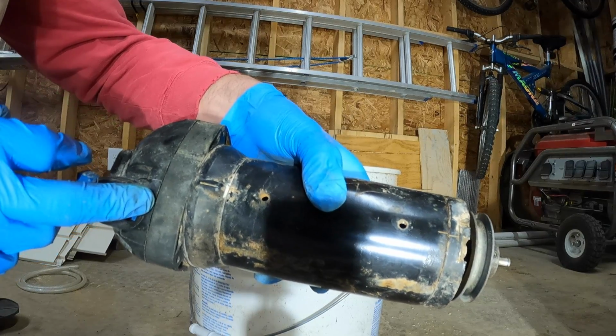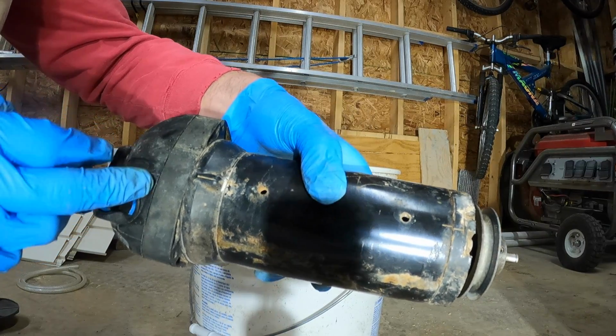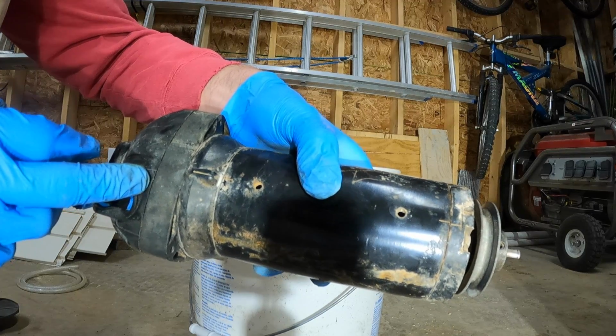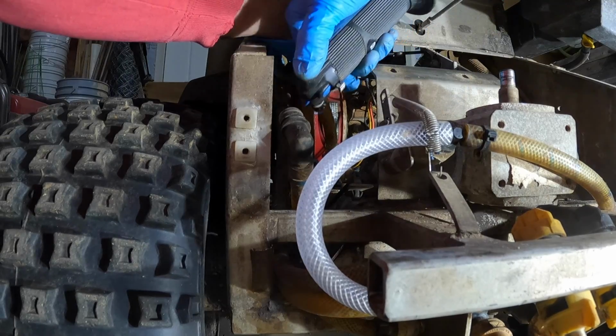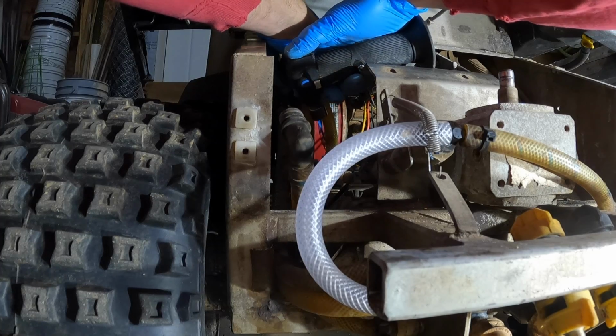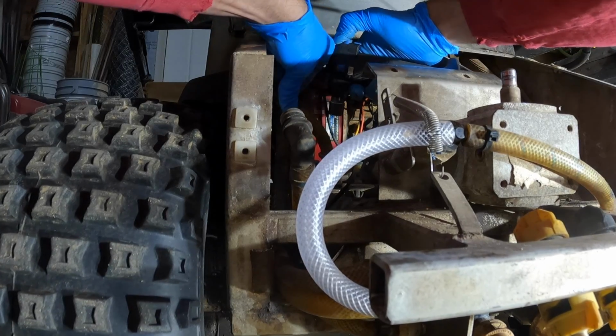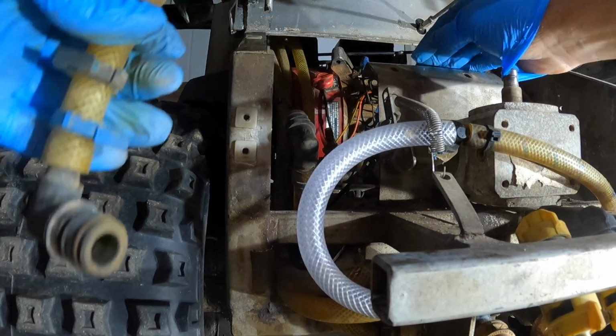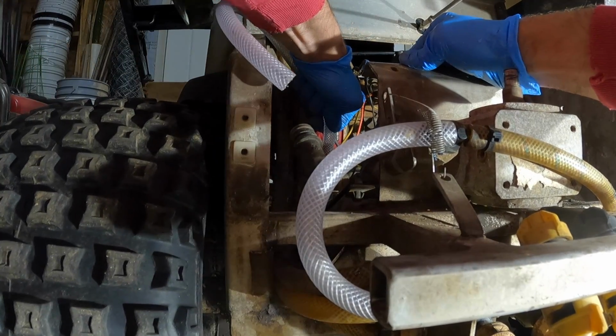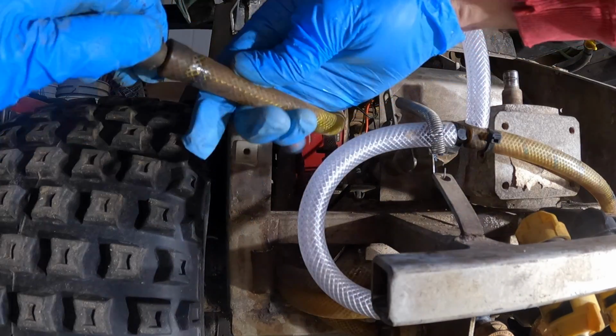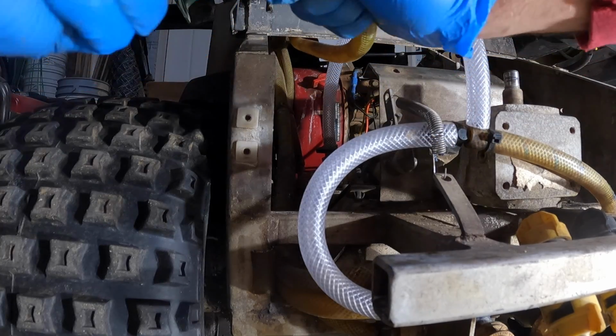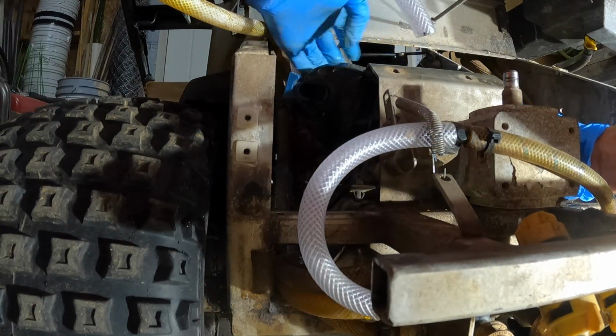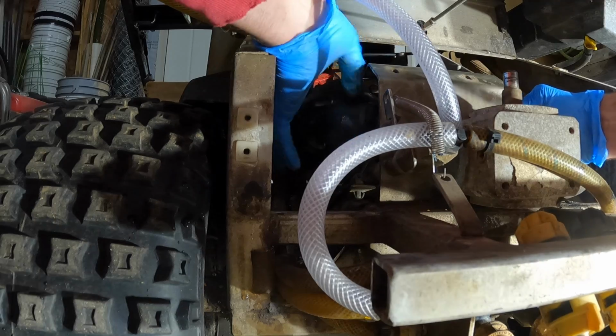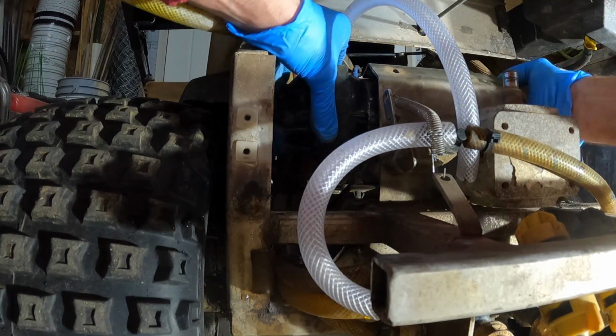That way it might help me eliminate some of the air out of the system, shorten up the intake line about 6 or 8 inches. So since we swapped the discharge line to the front of the pump, this discharge piece, I'm going to have to take it off, and we're going to add a longer piece onto it. And then the suction line, since it's closer to the tank, we're going to end up cutting this suction line off somewhere back in here to shorten it up. And hopefully that little loop will get rid of some of the air entrapment as well.